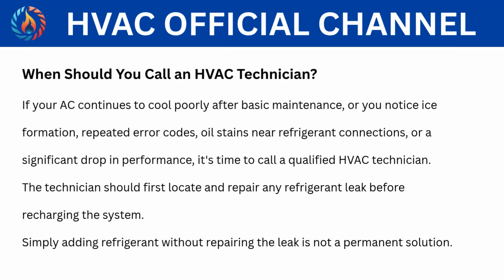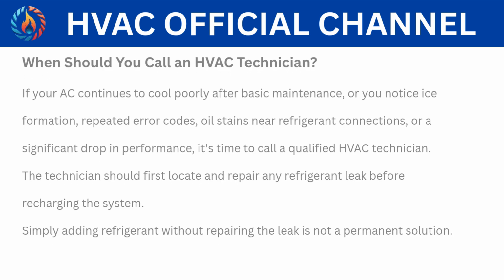When should you call an HVAC technician? If your AC continues to cool poorly after basic maintenance, or you notice ice formation, repeated error codes, oil stains near refrigerant connections, or a significant drop in performance, it's time to call a qualified HVAC technician. The technician should first locate and repair any refrigerant leak before recharging the system. Simply adding refrigerant without repairing the leak is not a permanent solution.